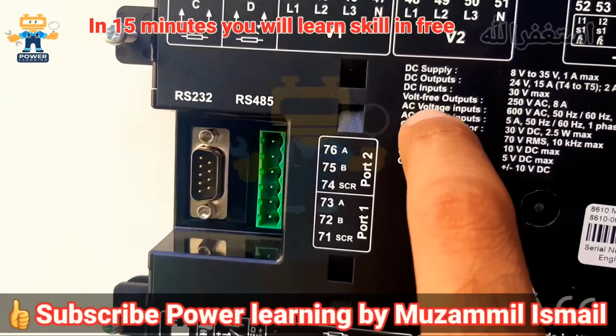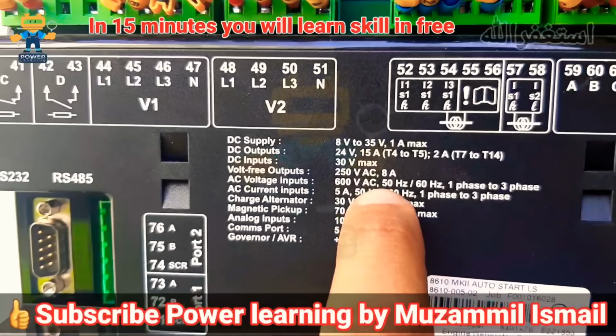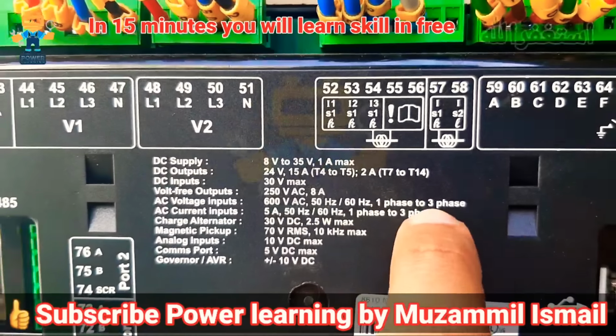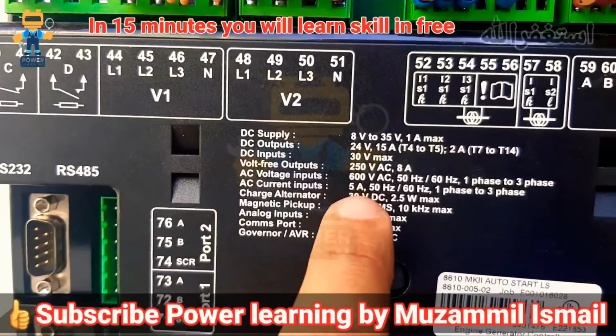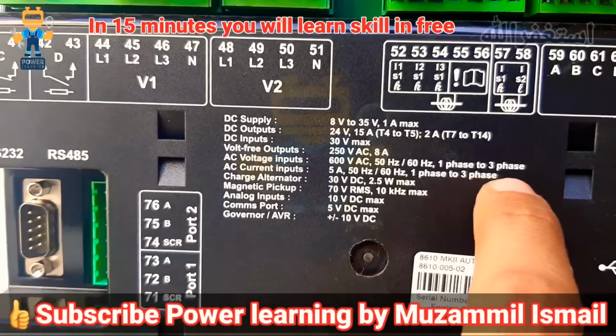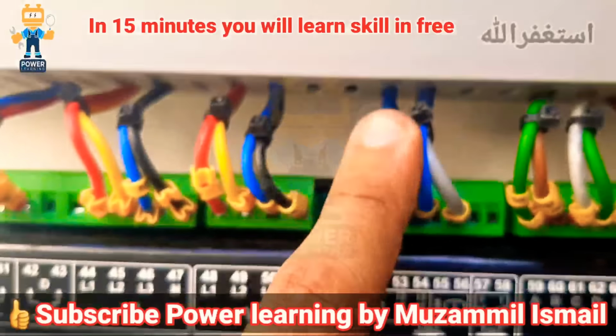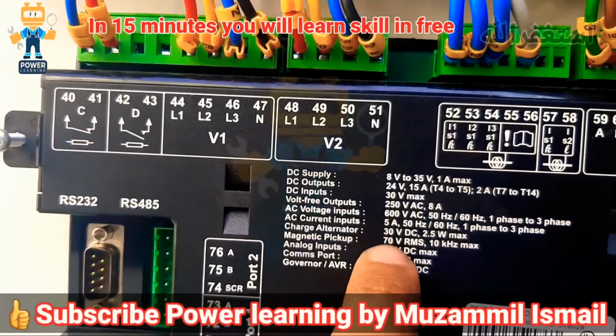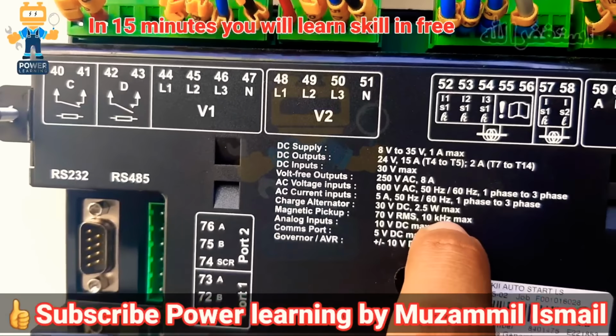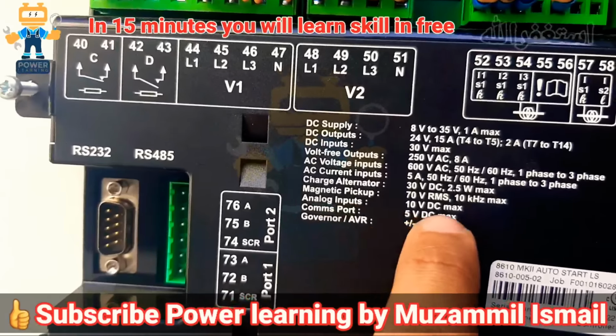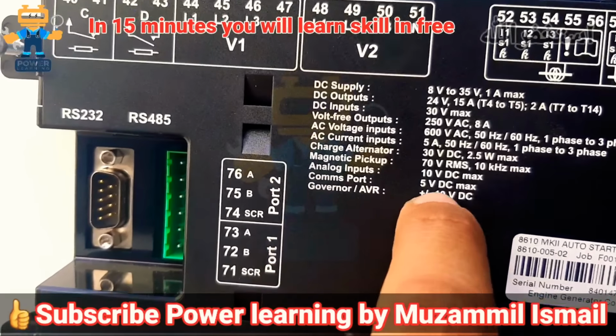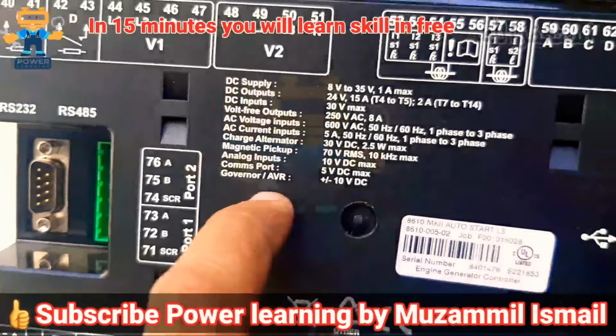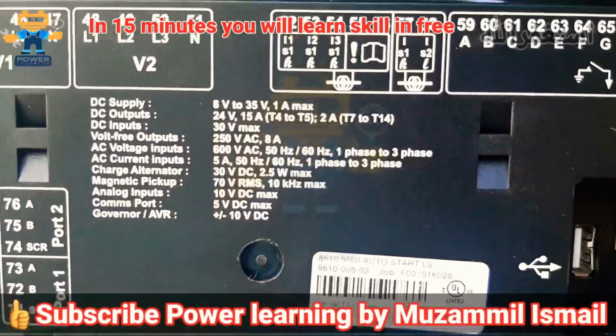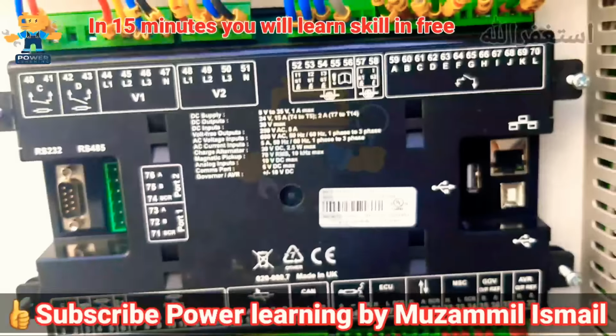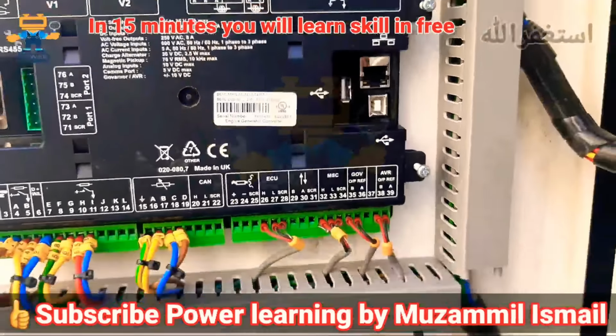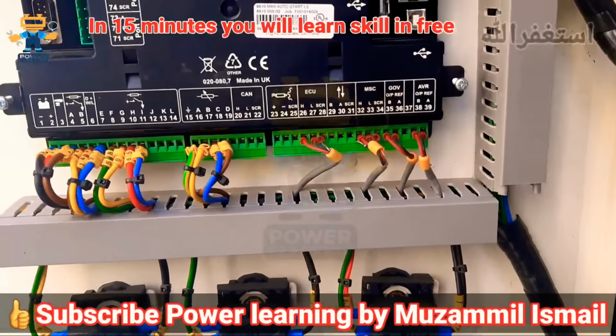Volt free outputs, these are our volt free outputs, and the rating is 250 volt AC 8 ampere. Okay, after that, AC voltage input is maximum 600 volt AC for low voltage, 50-60 hertz, 1 phase and 3 phase. Okay, AC current input is 5 ampere, 50-60 hertz, 1 phase to 3 phases, which is here. Okay, this one. Magnetic pickup 70 volt maximum, 10 kilohertz maximum. Okay, analog input 10 volt DC maximum, and comms port 5 volt DC. Okay, I already explained the governor and AVR plus minus 10 volt. So I think this is a video which you will understand very easily, and you can troubleshoot on any site with the help of this.